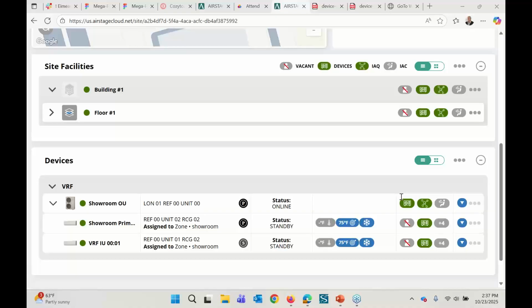So let's say they have a Metasys system or they have a Tridium system. What they find is the BMS is only going to be able to do set points and schedules of the VRF. It's not going to tell you how the VRF is operating. So we have plenty of customers that even though they're talking set points and schedules with a BMS, they still install AIRSTAGE Cloud because they want the ability to do the remote function setting, the commissioning, and the service monitoring of the system.